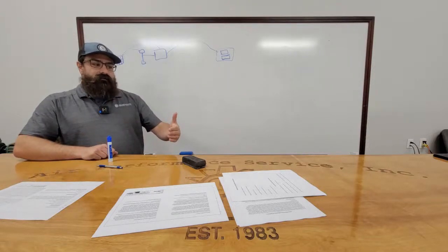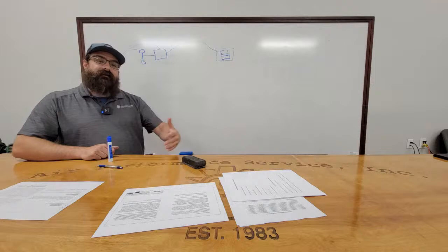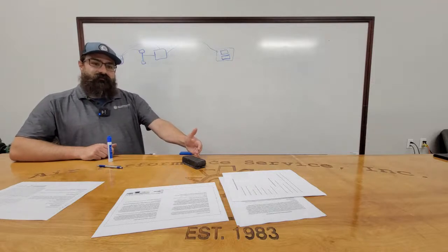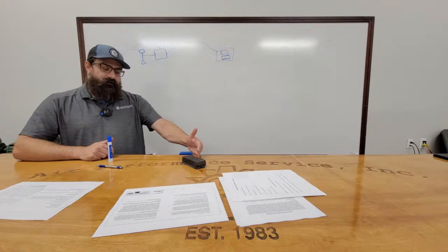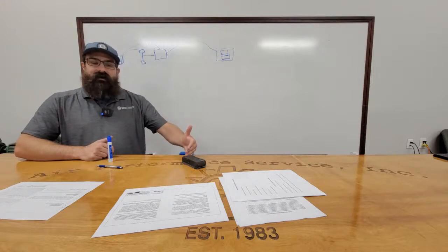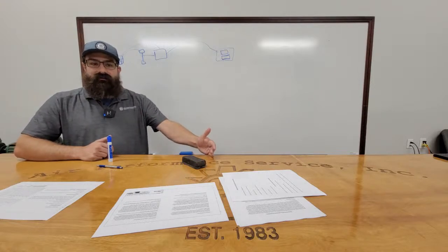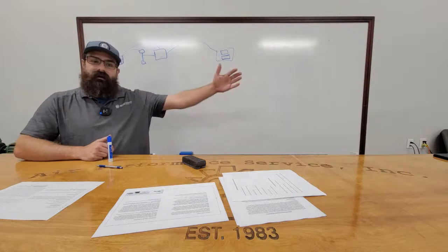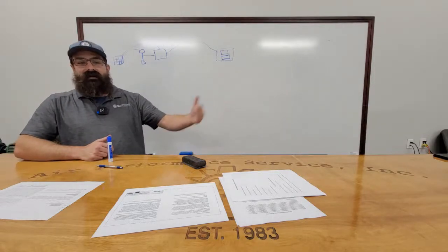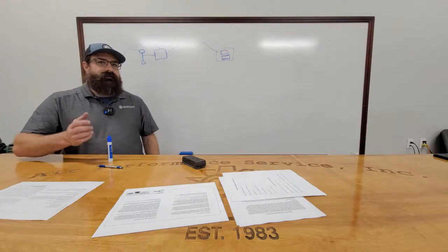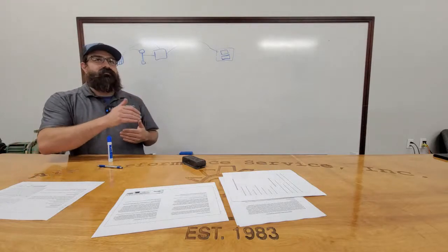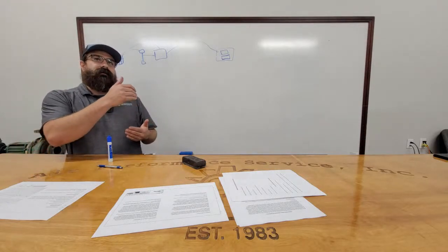Or some boxes will automatically come on and activate themselves in what they call a bypass mode or an unoccupied command. And we can say, all right, I've got 5 out of 25 boxes in bypass, bring on an air handler, right? And then once an air handler starts, a central plant starts, and so forth. There are a couple different ways, and it's really based on the systems.